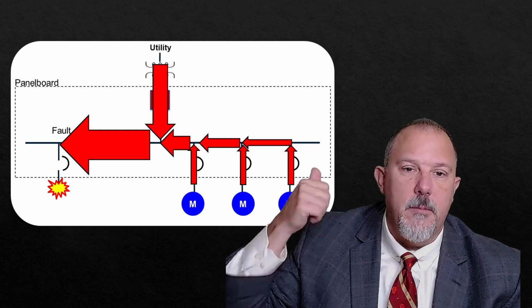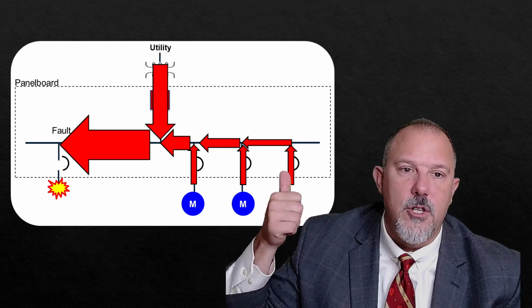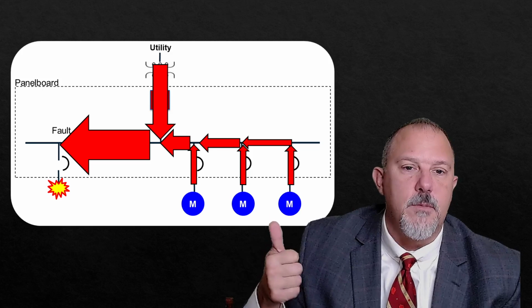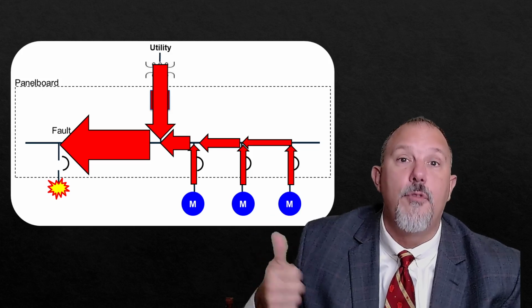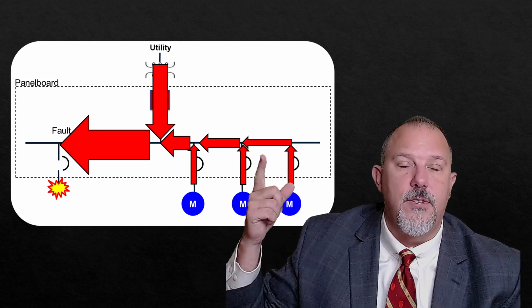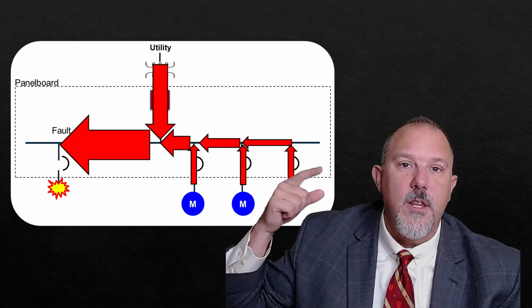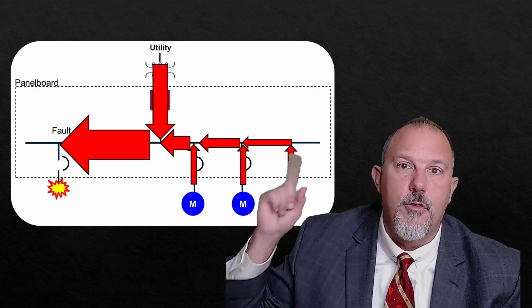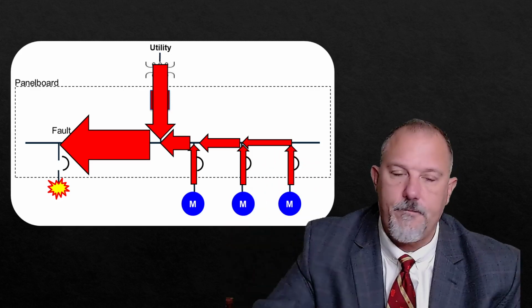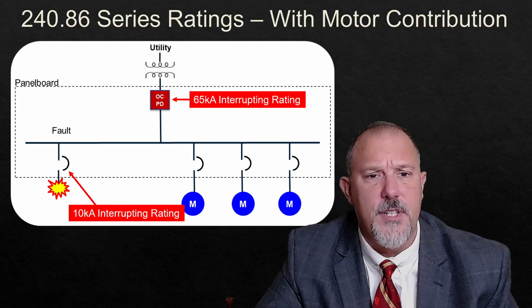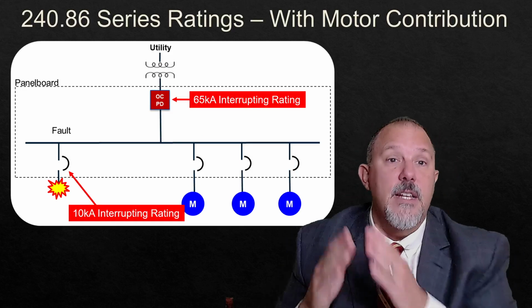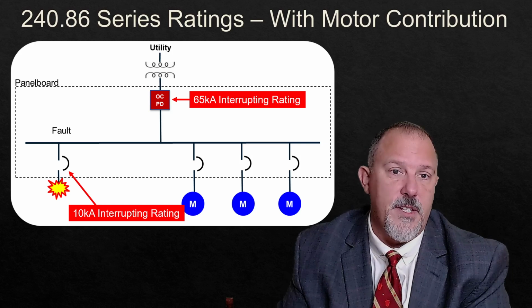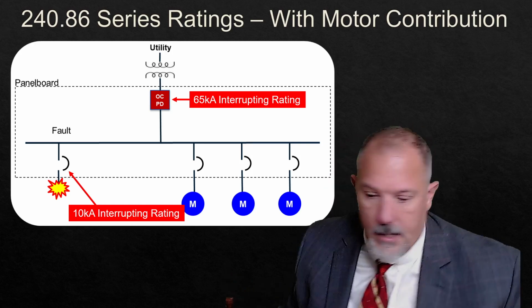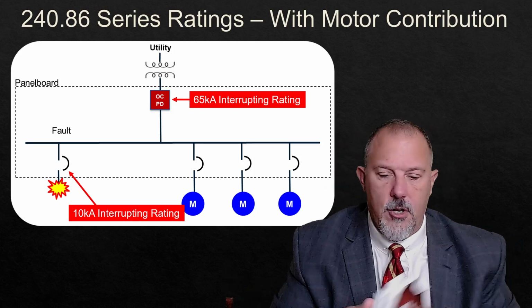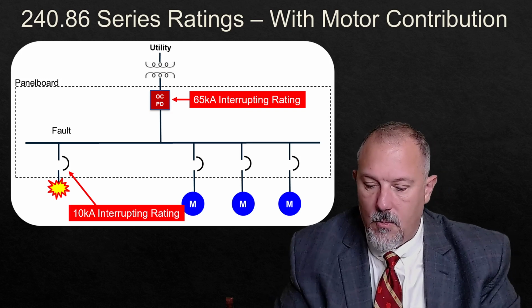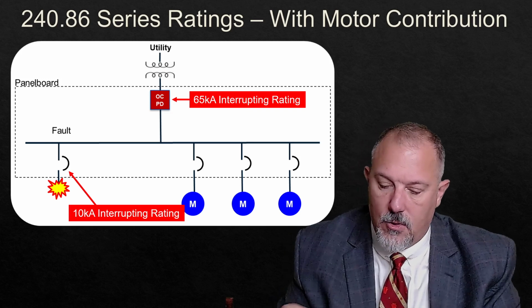The main circuit breaker in this example does not interrupt the currents that come from this motor, because the motor currents will not flow through that main overcurrent device. Only the current coming from the utility will flow through that main overcurrent device. It's an important thing to understand for a lot of different reasons. Series ratings is one of those reasons. Remember in the code in 240.86, I'm going to run over to 240.86 real quick.